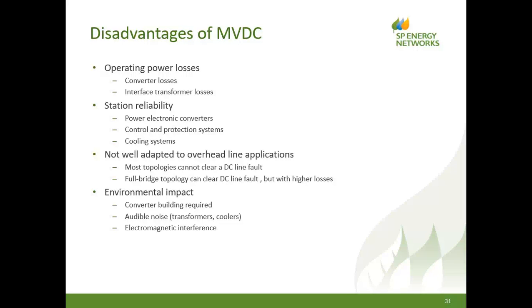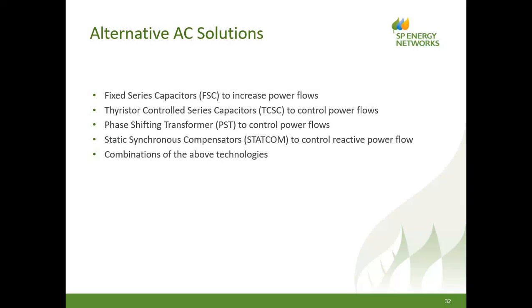And Kevin has mentioned electromagnetic interference. The conversion process from AC to DC, from DC to AC, does create harmonic distortion superimposed on the DC side, for example. We need to quantify that to find out what harmonic currents will be flowing in the cables, primarily across the Britannia Bridge. But also we need to look at the electromagnetic environment in general. We need to be aware of radiated interference, AC side harmonics, DC side harmonics. So there's a big learning exercise from the implementation of medium voltage DC into a UK distribution grid. If we go to the next slide, which is the last slide.